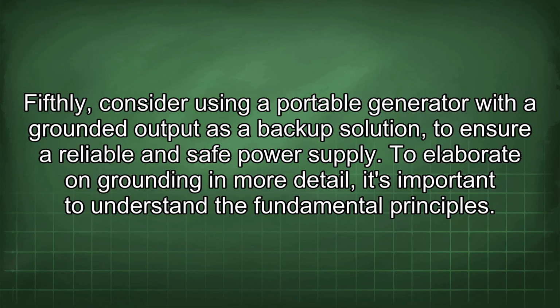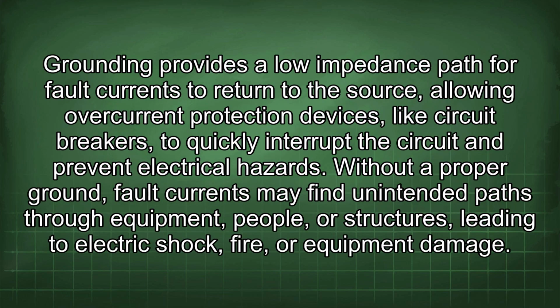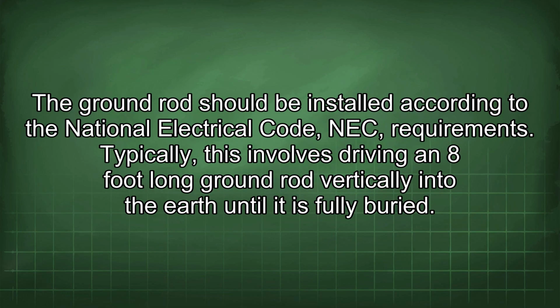To elaborate on grounding in more detail, it's important to understand the fundamental principles. Grounding provides a low impedance path for fault currents to return to the source, allowing overcurrent protection devices, like circuit breakers, to quickly interrupt the circuits and prevent electrical hazards. Without a proper ground, fault currents may find unintended paths through equipment, people, or structures, leading to electric shock, fire, or equipment damage. The ground rod should be installed according to the National Electrical Code (NEC) requirements.